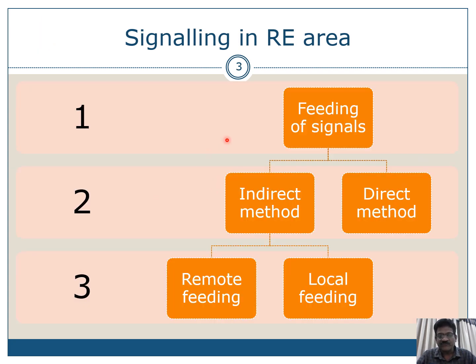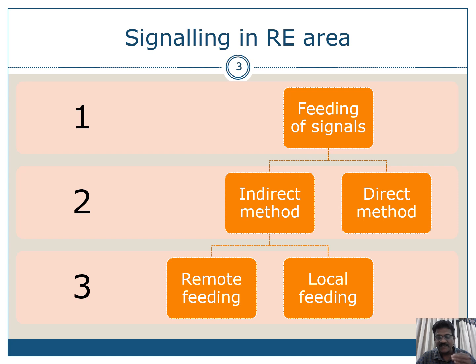There are two types of feeding: indirect feeding and direct feeding. Direct feeding means giving power supply 110 volts AC directly to the signal unit, while indirect method is giving 110 volts AC either through remote feeding or local feeding. Remote feeding means the power supply is going from relay room to the signal, while local feeding means 110 volts AC is already taken in the bus bar and available at the local location box of the concerned signal.